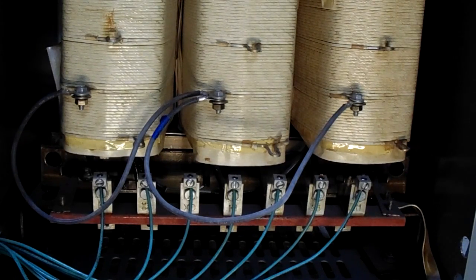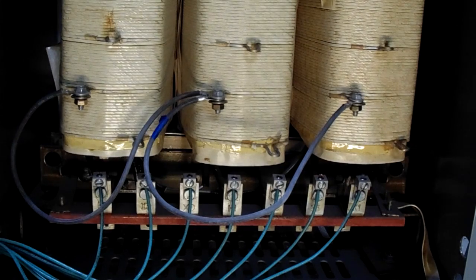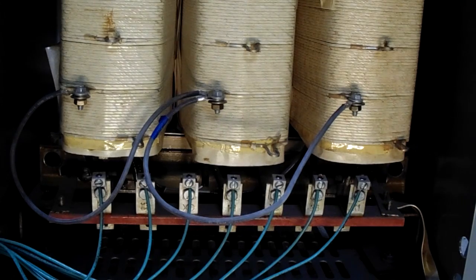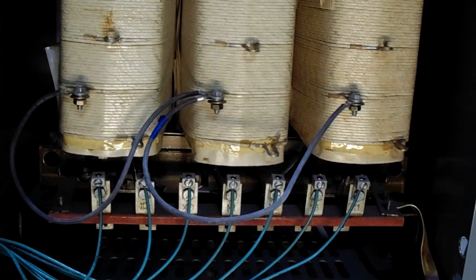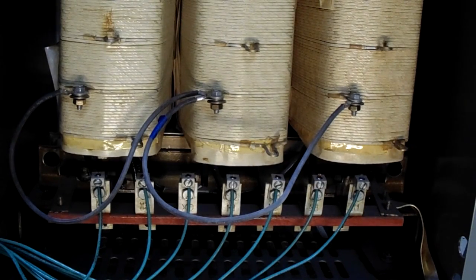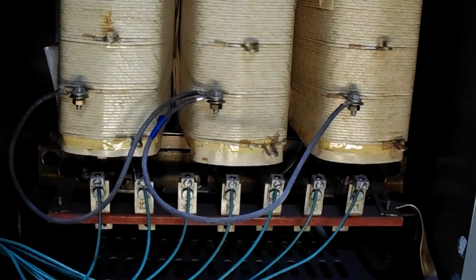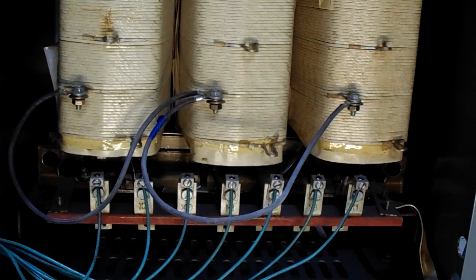I don't know how much you're going to need to derate it. It also depends on what temperature rise you're going to be within. But this is within a garage, so if I was running this thing all out, then it'll be in perfect conditions to be run at full load, because this is a 150 degree rise and 220 degree maximum insulation class. So this is fine as is.